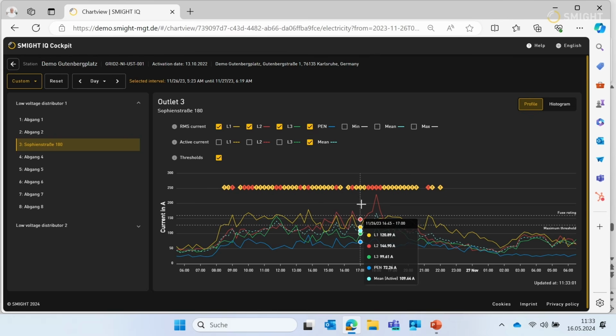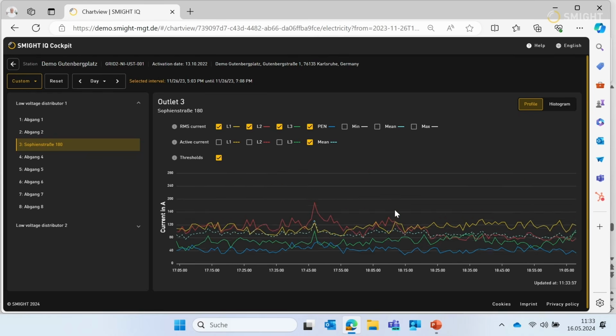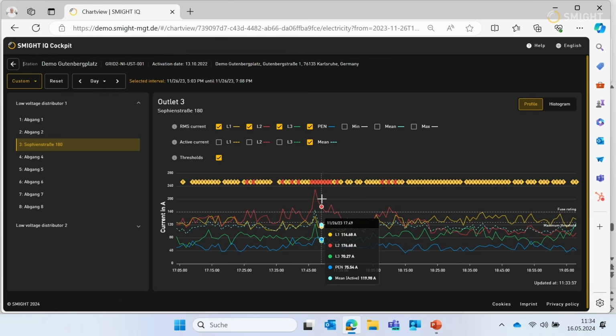If I have such a situation, what could I do as a grid operator? In this situation, I can identify that it's one particular phase causing the issue, so I could look in my data to see what's connected there and what I might do about it. But what this particular customer did is go out and perform a switching action to take the load and put it onto another feeder. So this was an overloaded feeder, and they did some switching to move the load to another feeder, reducing the load on this specific problem feeder.